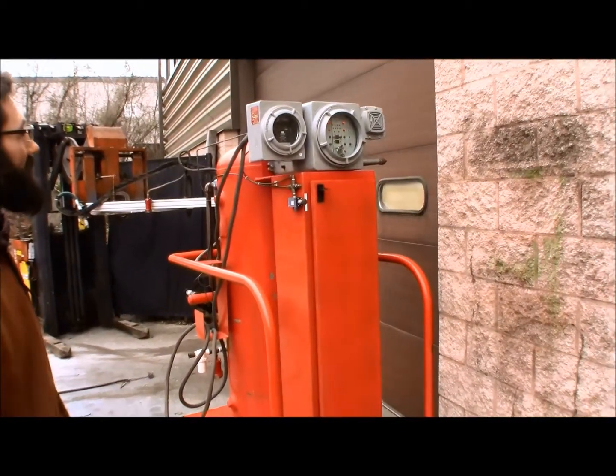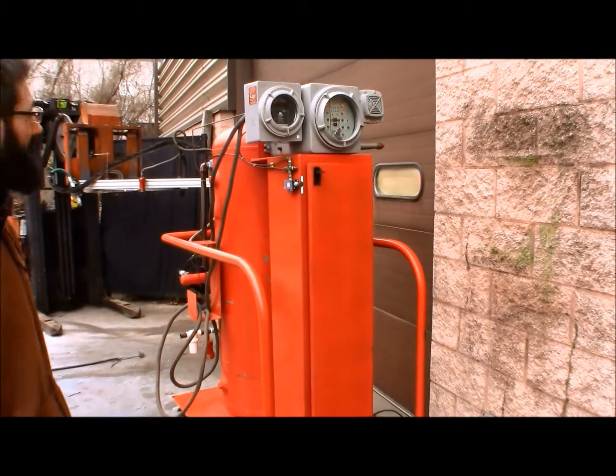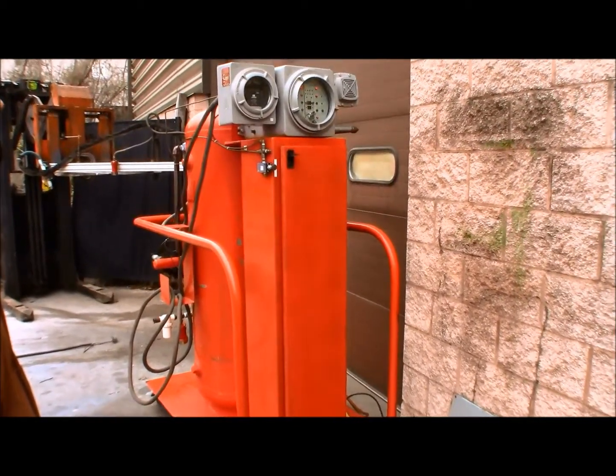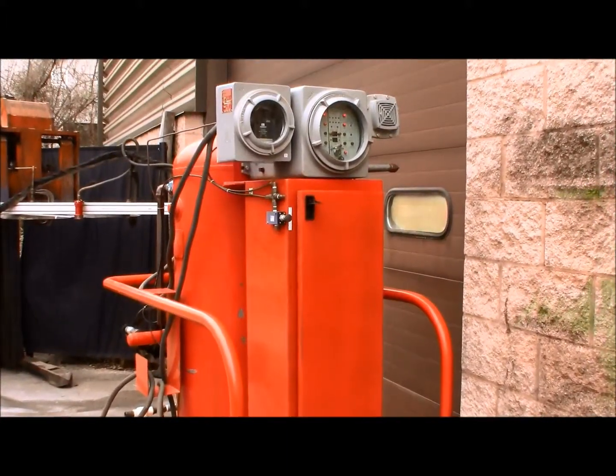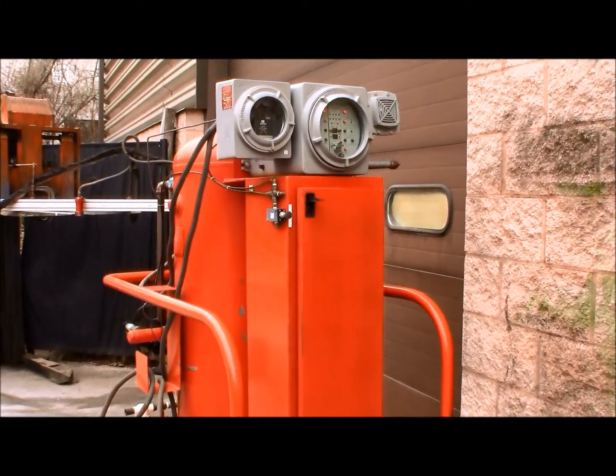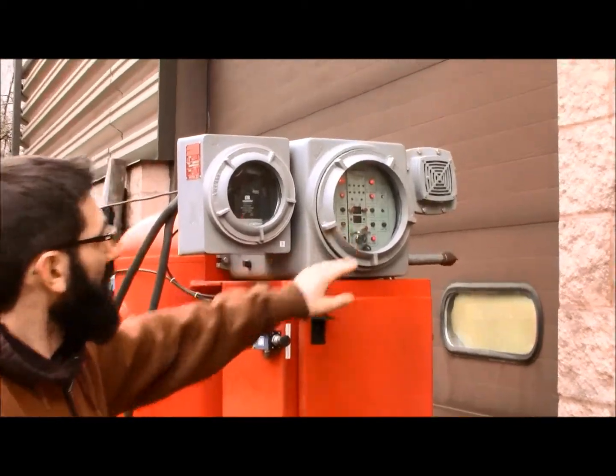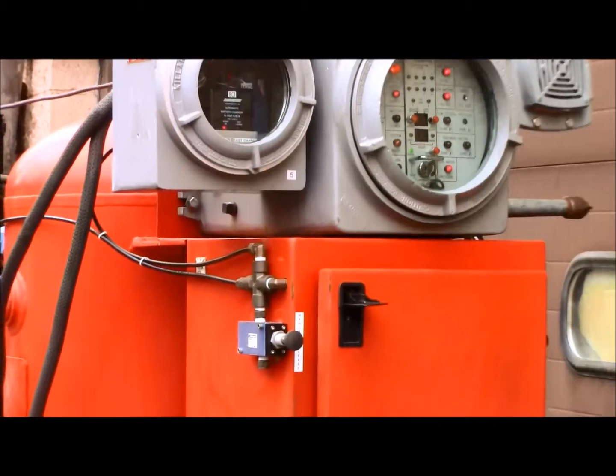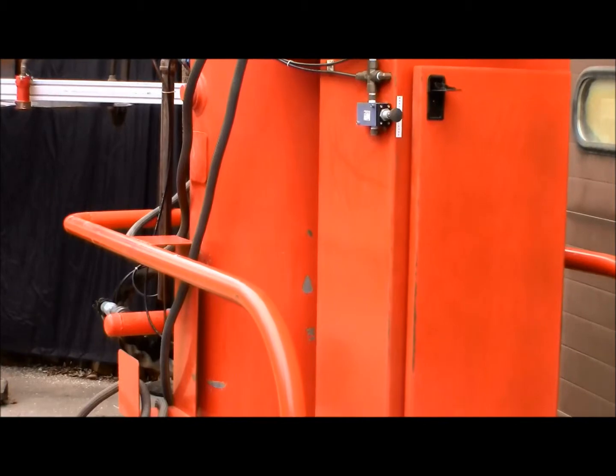Here we have a high-speed water deluge fire suppression system. The system uses ultraviolet sensors to detect any ultraviolet flame or arc, and once the sensors see the arc, they send the signal back to this controller. The controller will then fire some solenoids and open up the nozzles on the fire heads.